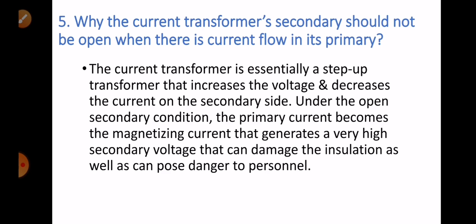The next question: why should the current transformer's secondary not be open when there is current flow in its primary? The current transformer is essentially a step-up transformer that increases voltage and decreases current on the secondary side. Under open secondary conditions, the primary current becomes the magnetizing current, which generates a very high secondary voltage that can damage the insulation and cause danger to personnel. This is the reason the output of a current transformer is shorted, not kept open.